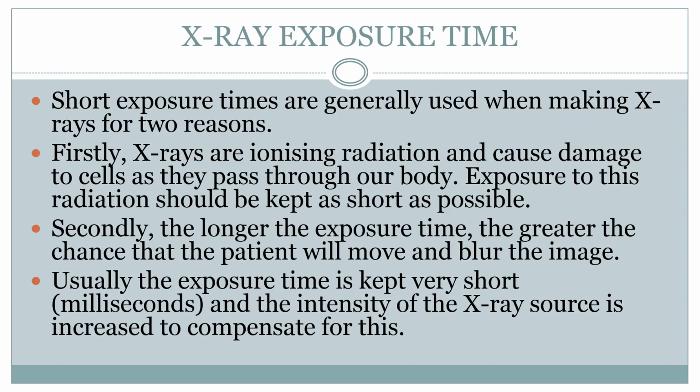And the last factor we need to consider when tuning an X-ray is the exposure time. These days we generally use short exposure times when we take X-rays. That first image at the beginning of this PowerPoint, Röntgen's image of his wife's hand in 1895, I believe it took about 15 minutes to take, which is quite a long period of time, whereas modern X-rays generally take just a couple of milliseconds.